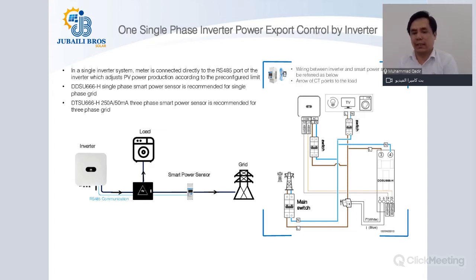So in case there is power going towards the grid, the current will be sensed, and in that scenario, the inverter will immediately respond and reduce its output power equivalent to the load requirement, such that there is no power going towards the grid.